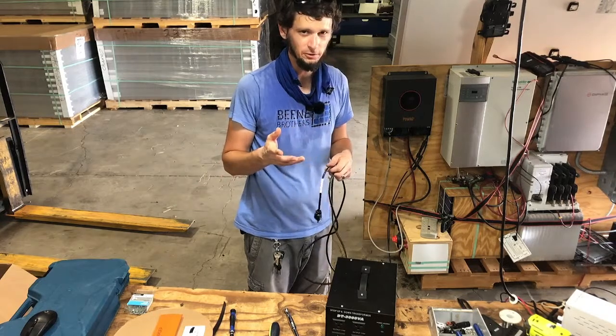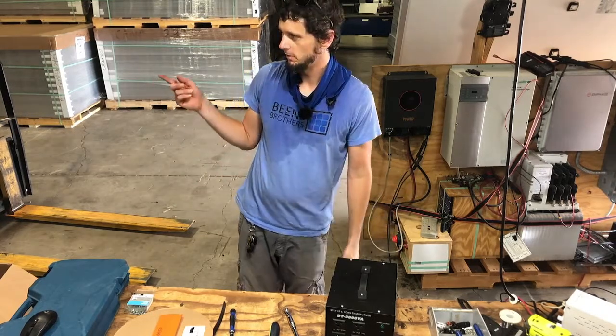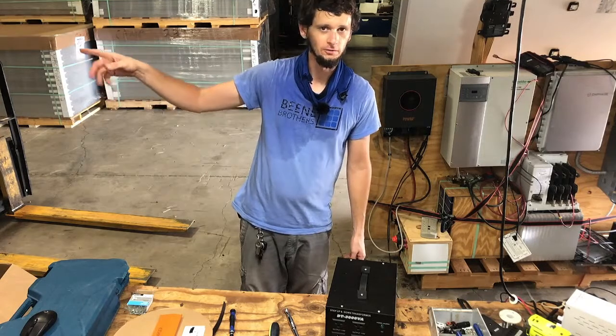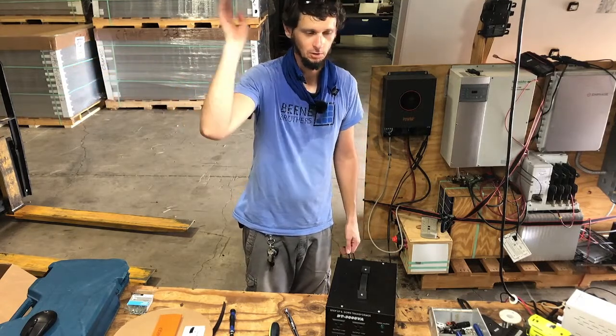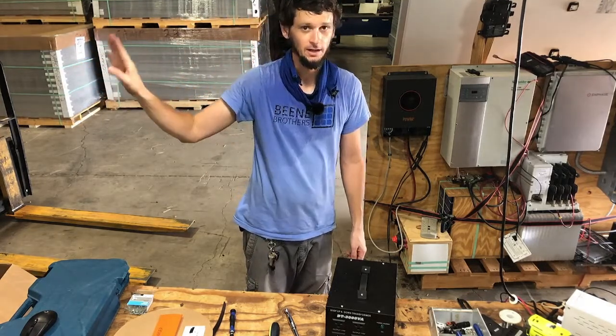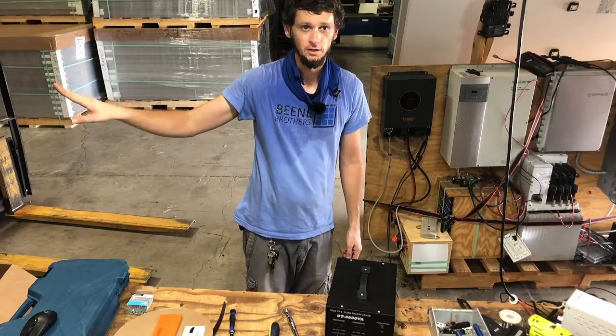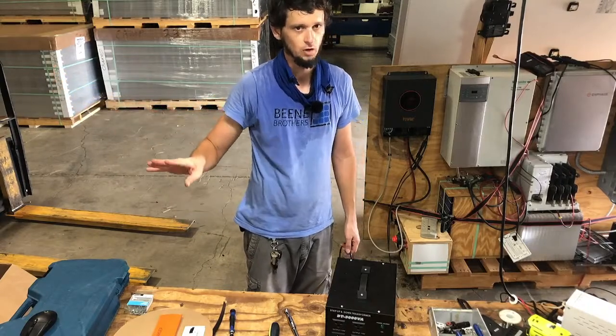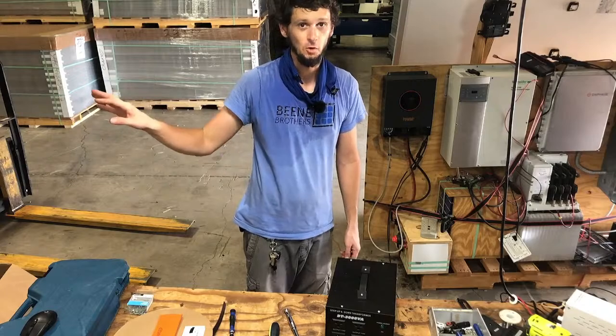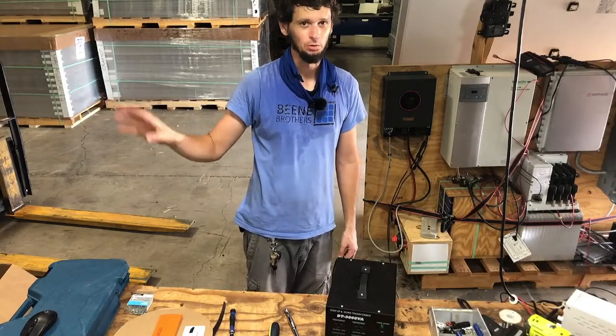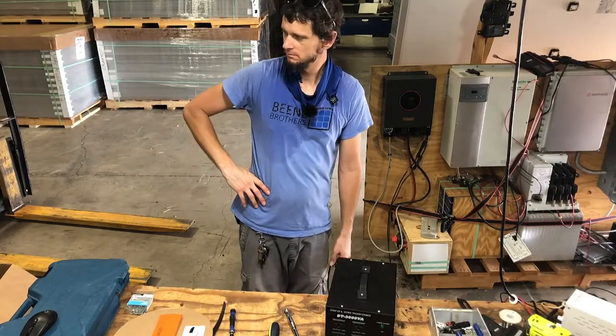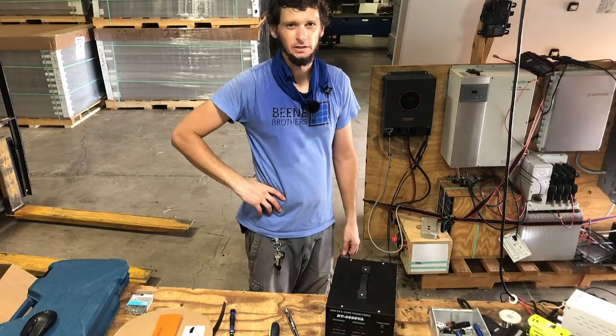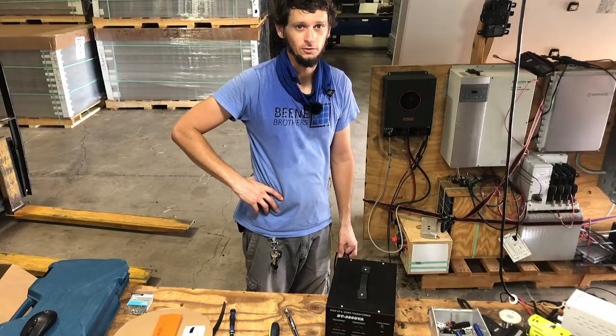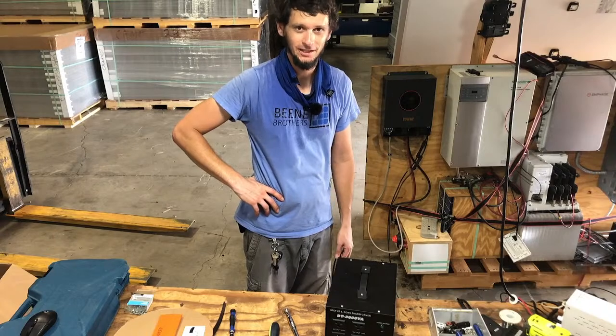Wouldn't be that big of a deal if it was just like a 3,000 watt inverter. I have a squirrel cage fan over here from my 5-ton air conditioner that I saved to blow air through the house, and I usually run it at 120 volts, so it's just breezing on me now. It's great. But if you connect it at 240, oh boy, it pulls a lot of wattage. I think it was pulling like 2,000 watts at 240 volts. I was like, that's good, that'll test an inverter a little bit.